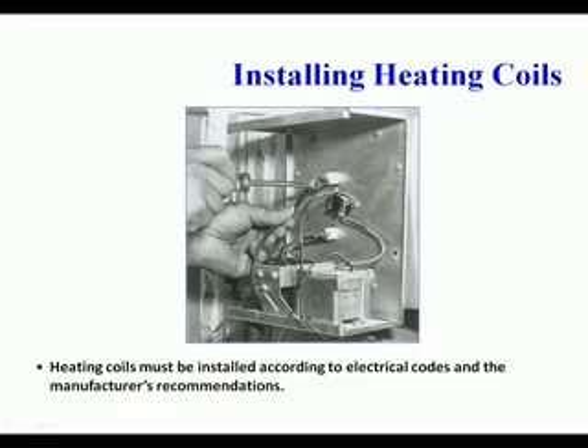When you install heat coils, there are a few procedures that have to be followed. First, heating coils must be installed according to electrical codes and the manufacturer's recommendations. Electric heating installation must be carefully checked. Be certain it's fire safe and safe for humans and animals as well as efficient. Baseboard heaters must have unhampered air circulation. Unit heaters must not be installed dangerously close to flammable materials or surfaces. Furnace units must be shielded electrically and heat protected. All metal parts of the furnace must be grounded.